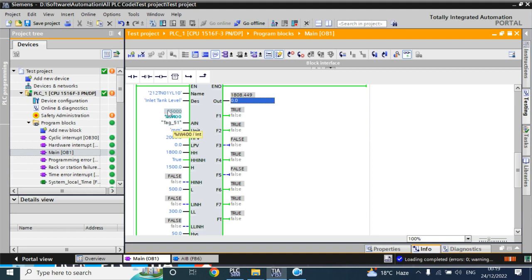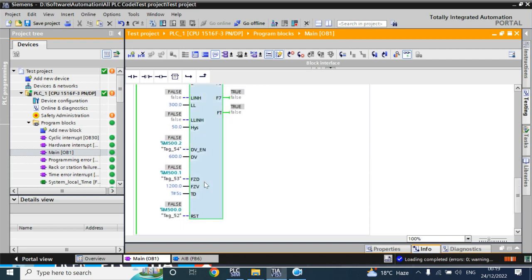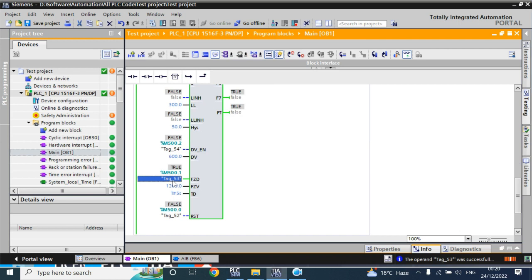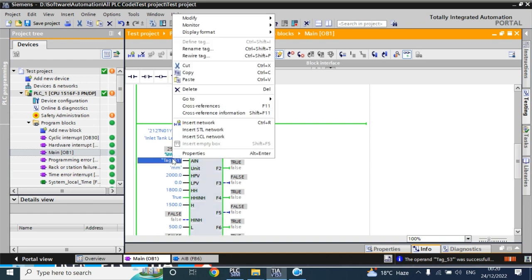Currently the input from the device has a count value of 2500, so the calculated output is 1800. Now I want to freeze the value — the frozen value is 1200. I'll click to set freeze to true. The output value should now be 1200 — yes, it is 1200.